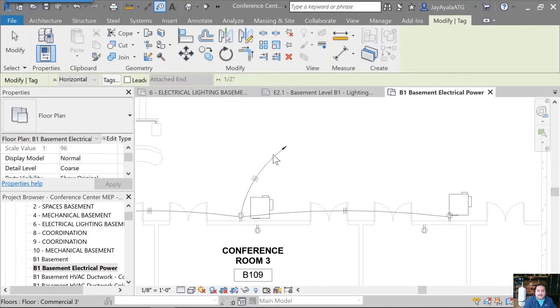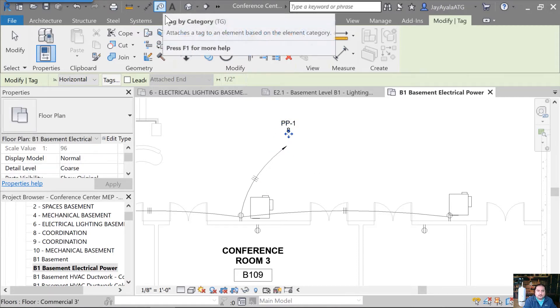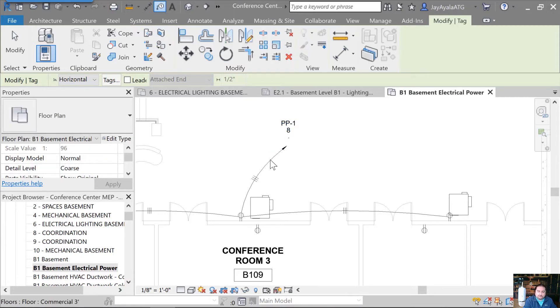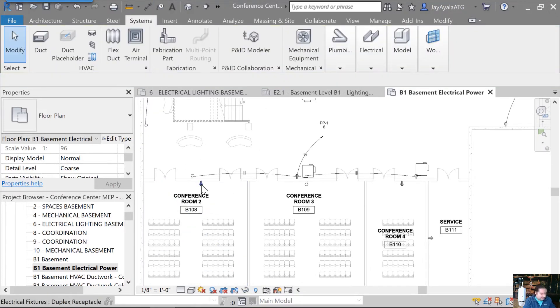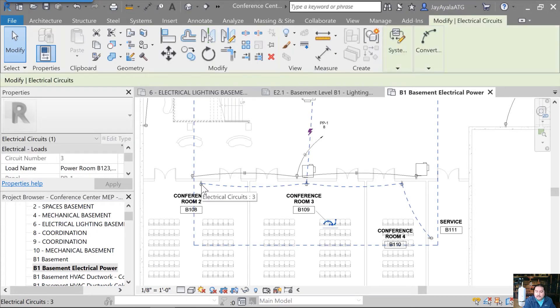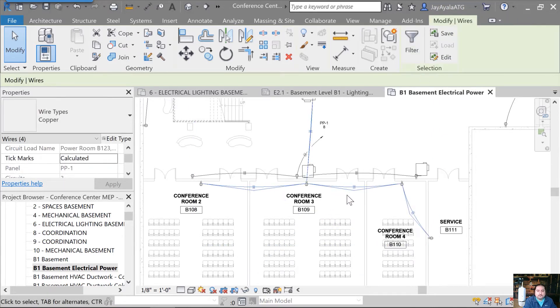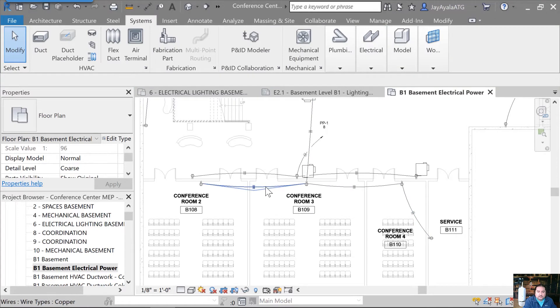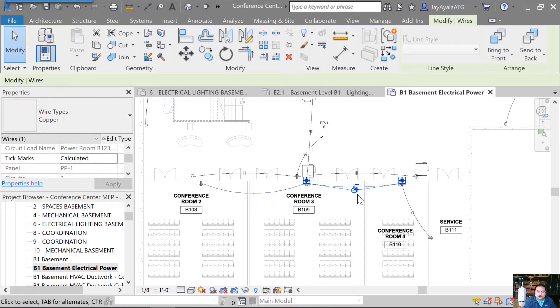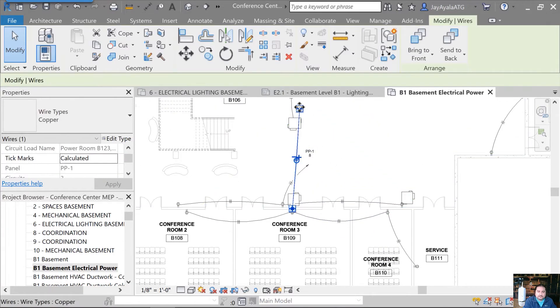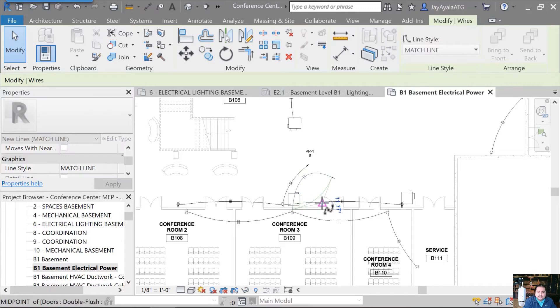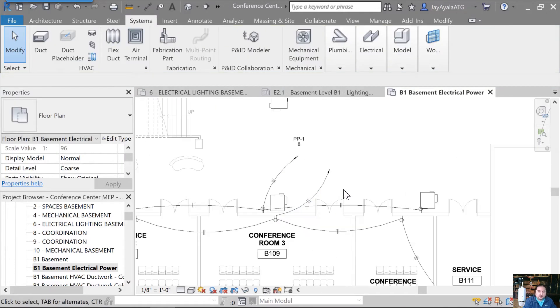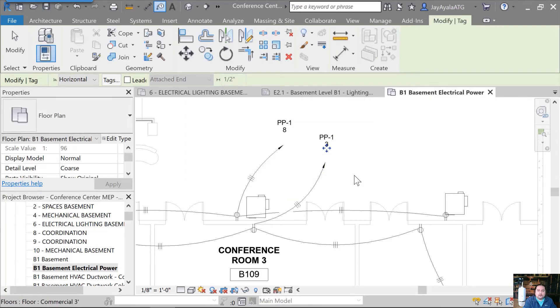I can add arc to wiring just like that. I can add the arc wiring. Now that layout may not be very efficient. So you can pull this down and by leveraging the vertex over here, you can direct the arrow in the direction that you want it to go. Finally, we can add the tag feature, tag by category. And that home run is now telling me that this is circuit on power panel one circuit number eight. So let's do that one more time. I'm going to show you a different way to do it this time. I simply hover over that outlet and I click. Now, when I click the left mouse button, I get these two buttons down here. Earlier you saw me go to the contextual ribbon. Now I'm just going to use this feature right here.